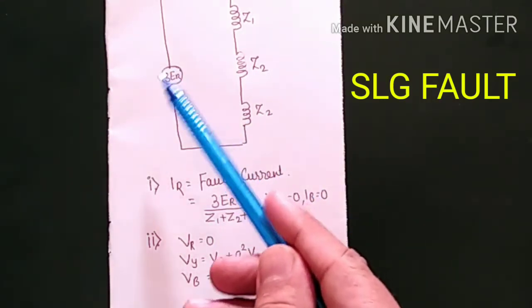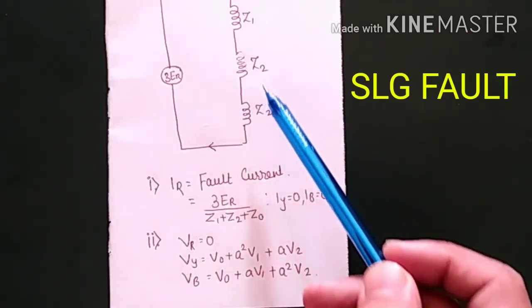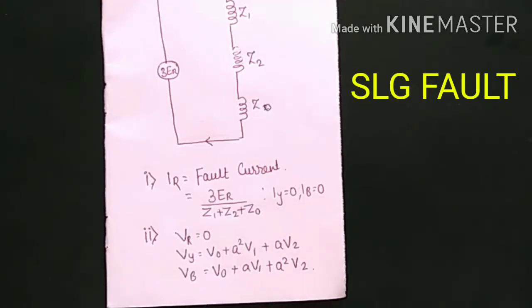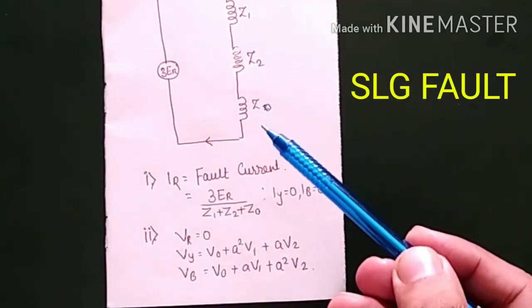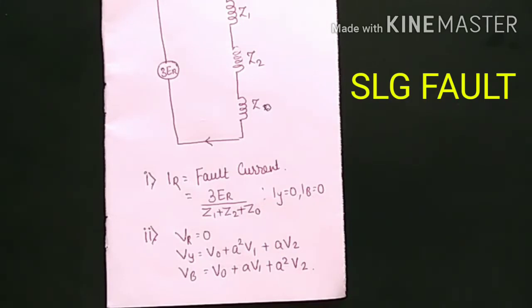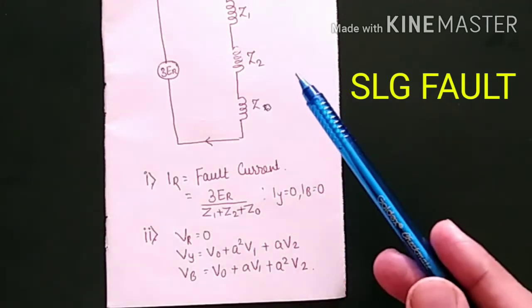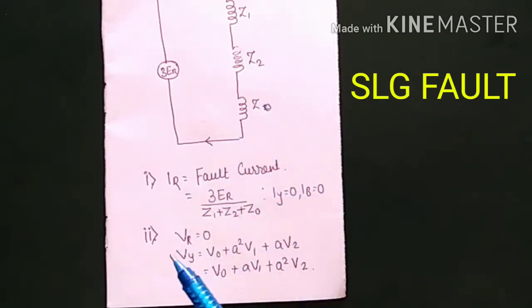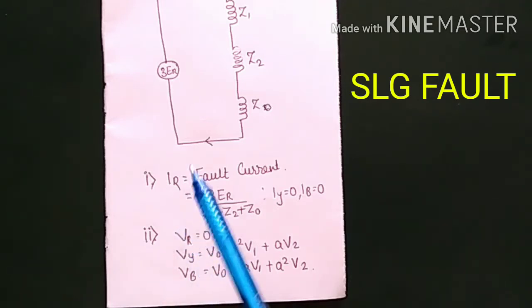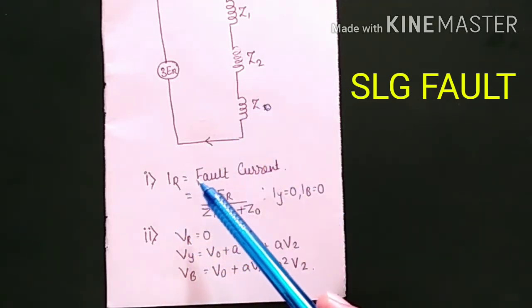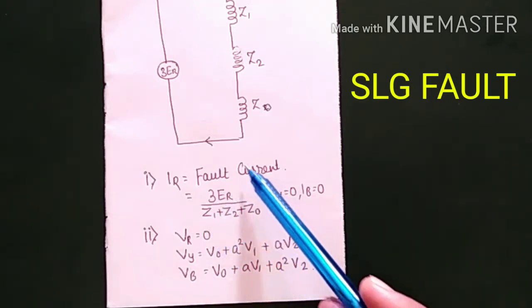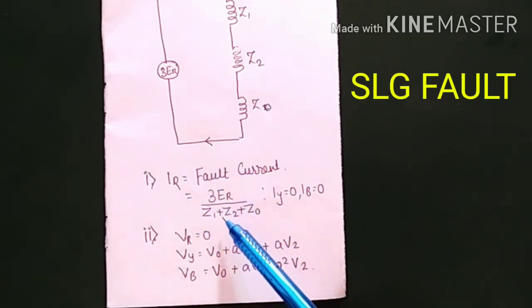This is the 3ER voltage in series with Z1, Z2, and Z0. Z1 is the positive sequence, Z2 is the negative sequence, and Z0 is the zero sequence impedance. If there is a fault impedance also, we have to add plus 3ZF. The fault is occurring on R phase, so IR is the fault current: IR = 3ER / (Z1 + Z2 + Z0). This is the formula for fault current in single line to ground fault.